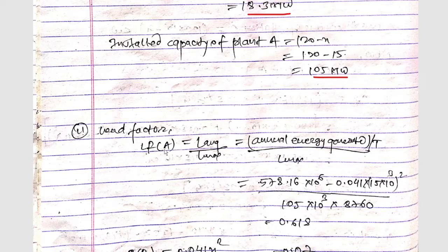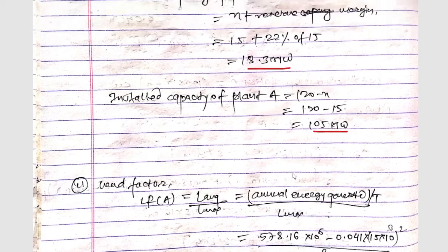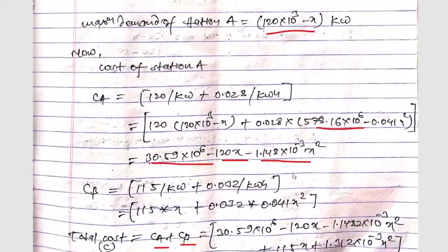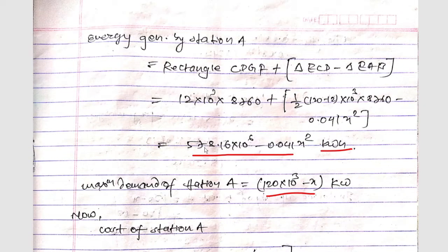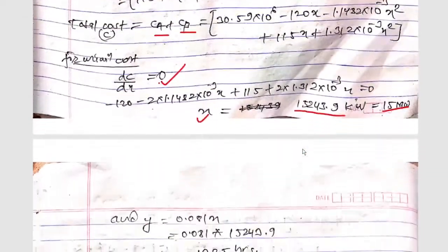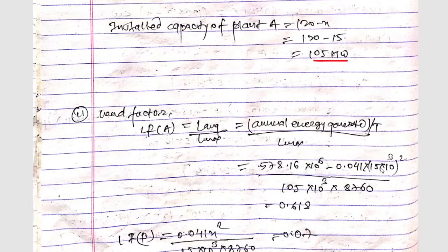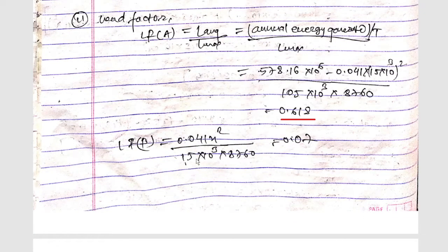The load factor of plant A = annual energy generated / (L_max × T). EA = 578.16 × 10⁶ − 0.041X², substituting X = 15 MW, divided by L_max = 105 × 10³ kW and T = 8760 hours, gives load factor of A = 0.618. For plant B: EB = 0.041X² divided by 15 × 10³ × 8760, giving load factor of B = 0.07.